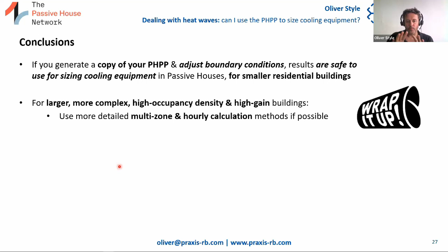For larger, more complex buildings, especially with high occupancy density and high gain areas, you're going to want a more detailed multi-zone and preferably hourly calculation, to make sure you can meet the cooling loads at different points in the day in different areas.